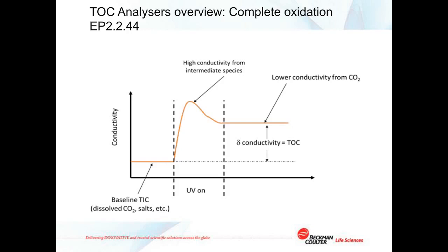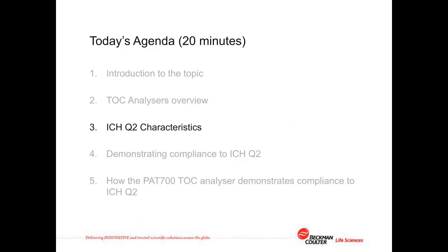If the molecule is not completely oxidized, carbon atoms can remain trapped inside the organic molecule and will not be measured, causing you to under-report TOC. So if a TOC analyzer is to be used for product release testing data, it should follow the requirements of ICH Q2 in just the same way as a laboratory QC TOC analyzer must.